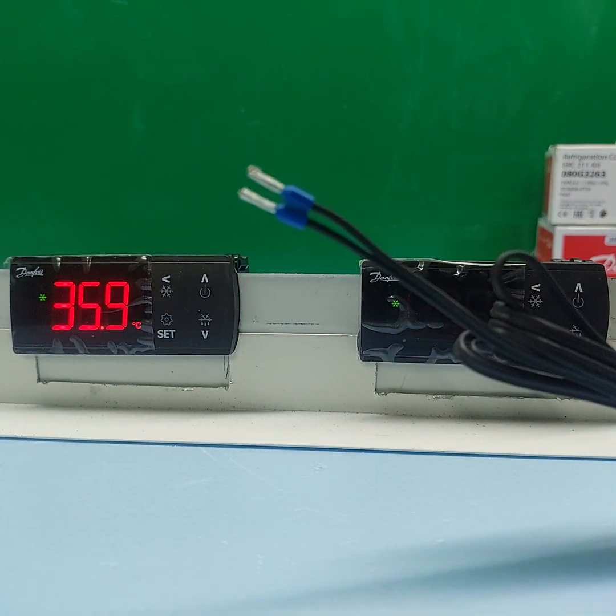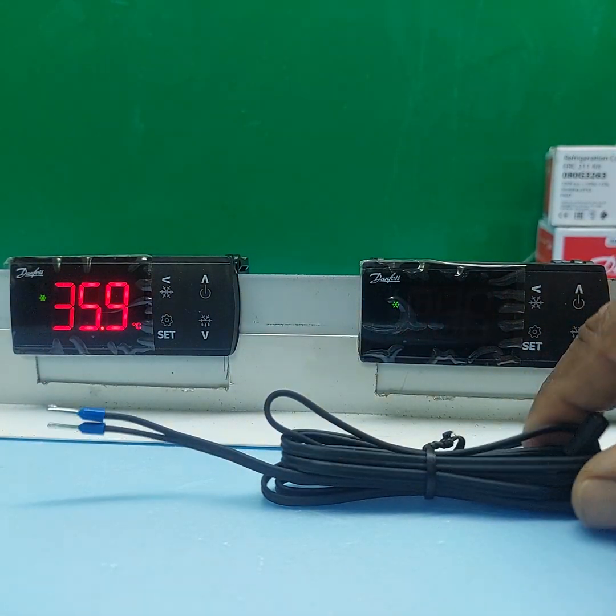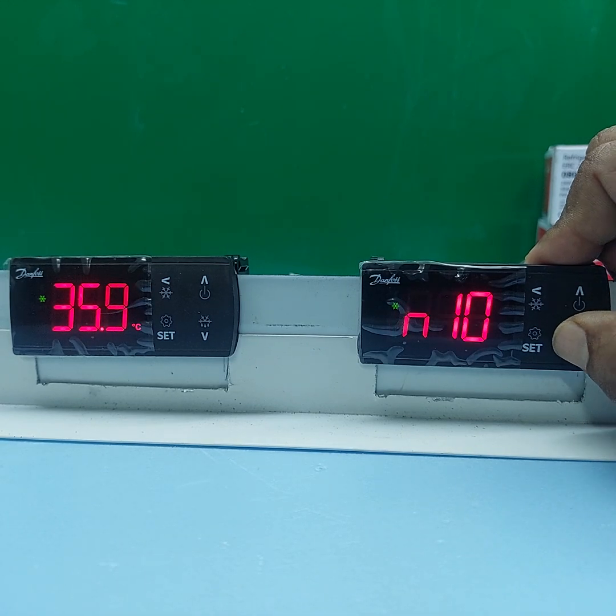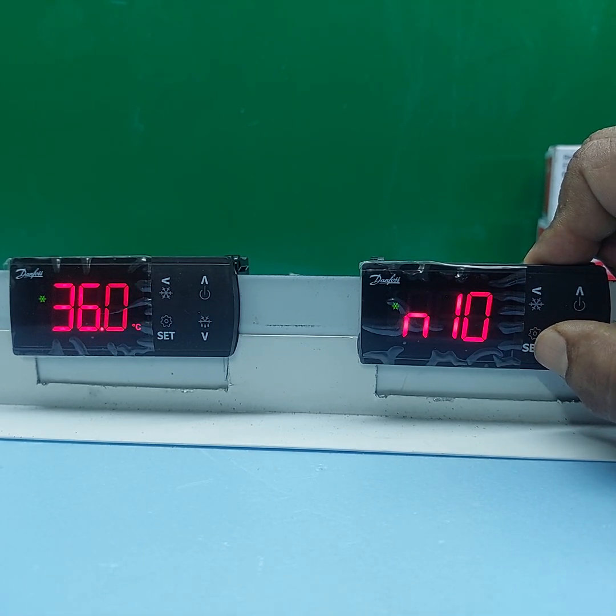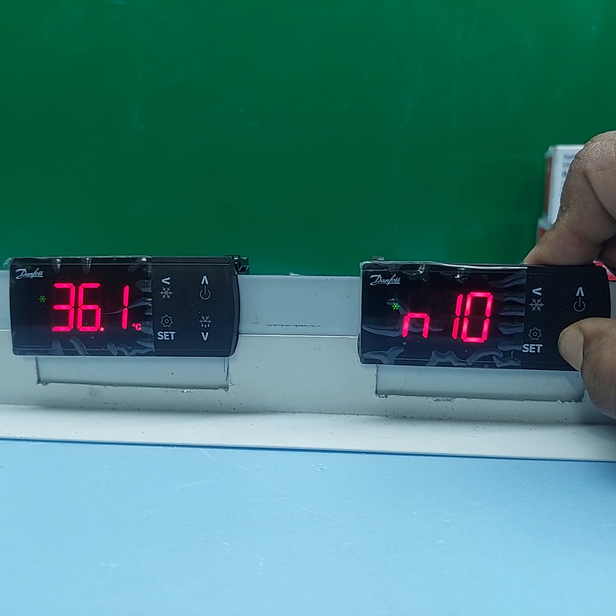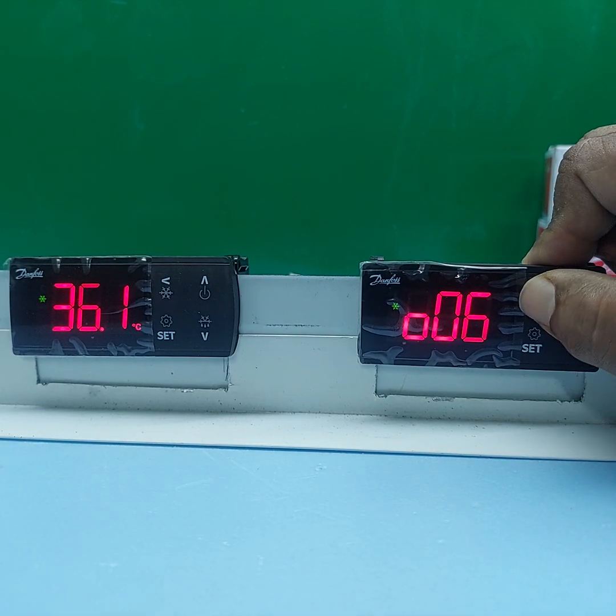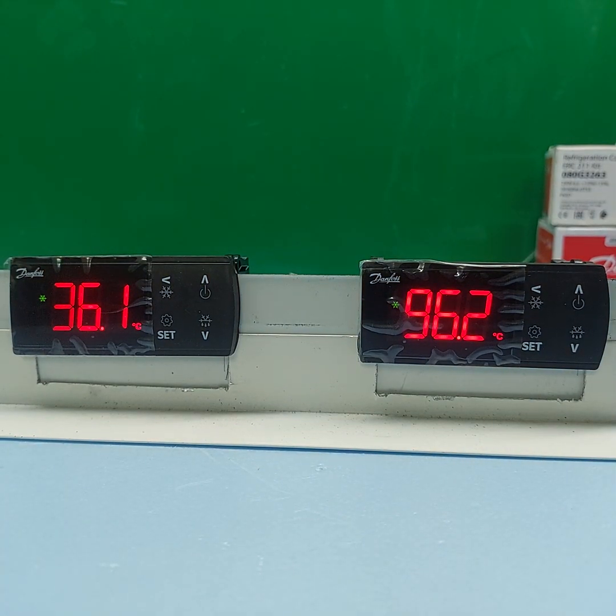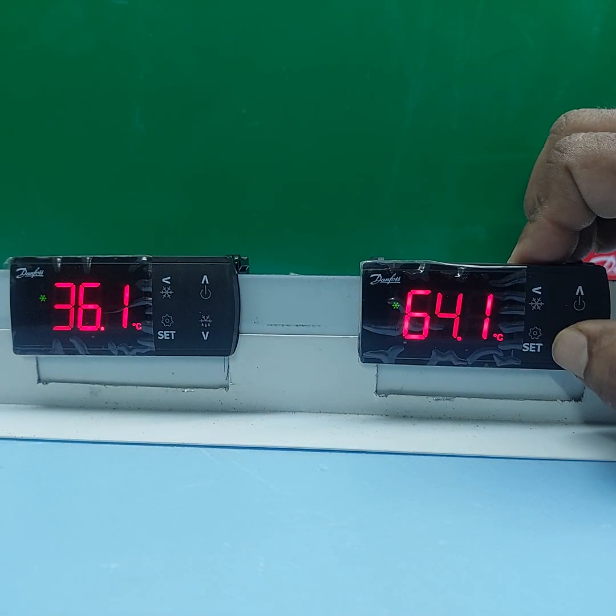This type of sensor is N5, N10. Now we use another one. We check which sensor this. There is three more setting, sensor selection. This is N10. Now we go to another selection, N5. We check N5. Return to menu. N5 going to down. N5 is showing 64.1 degrees centigrade. We will check another, select another one.